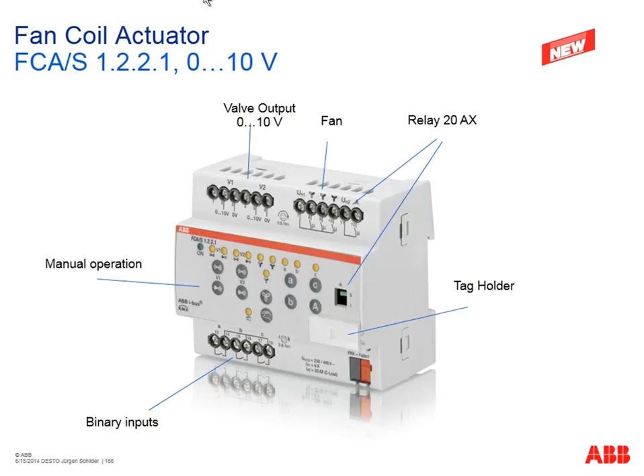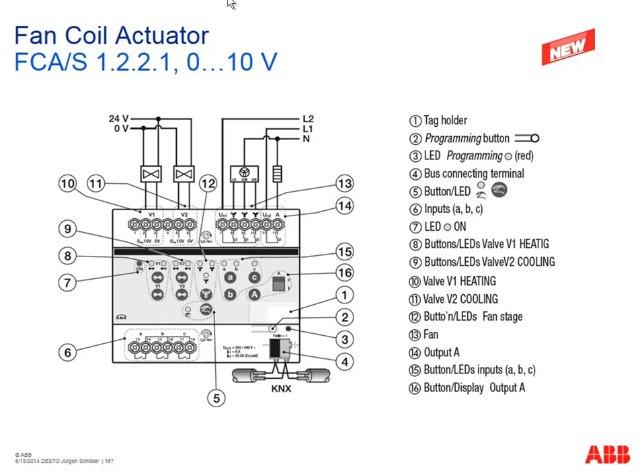Here, about the wiring diagram, you can see on the left side what is different. Here we have our analog output signal between 0 and 10 volt to control our valve drive, and here the valve drive for heating. Everything else, the motor or the fan with up to 3 speeds, electrical heater and so on, is still the same.